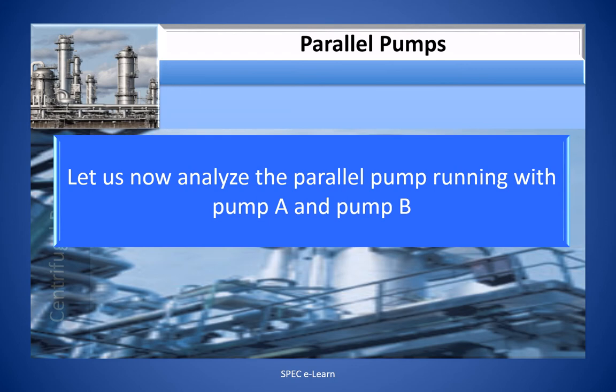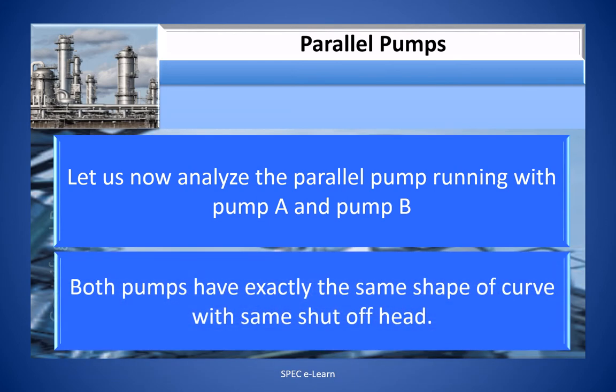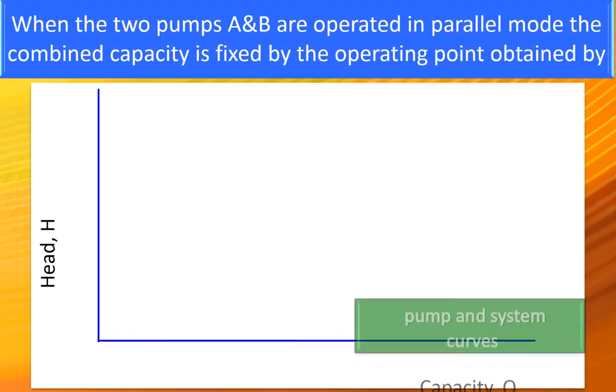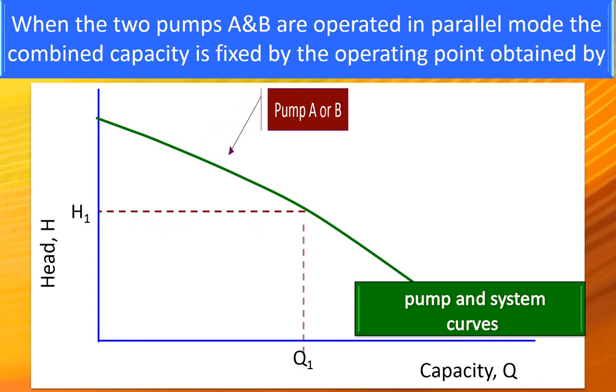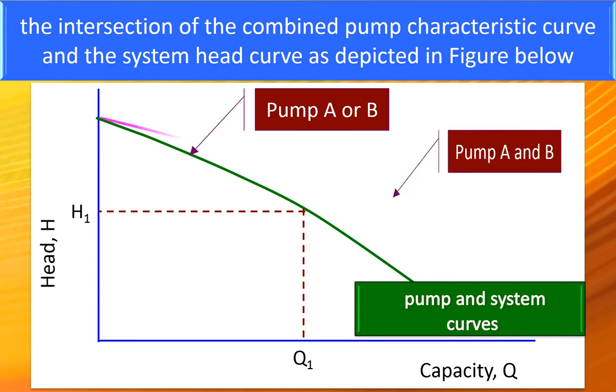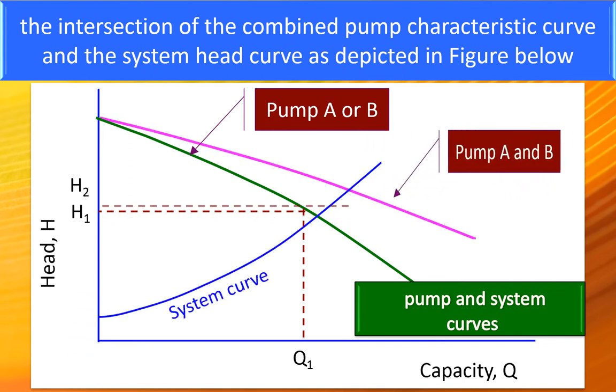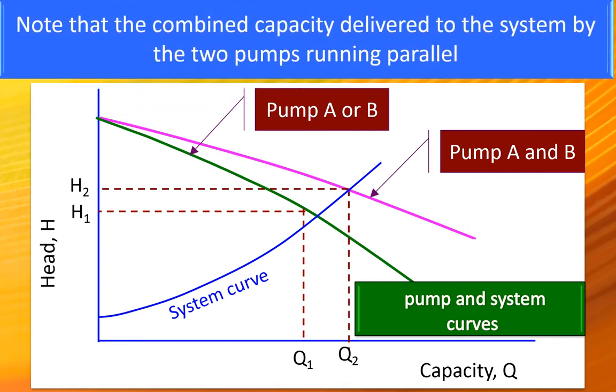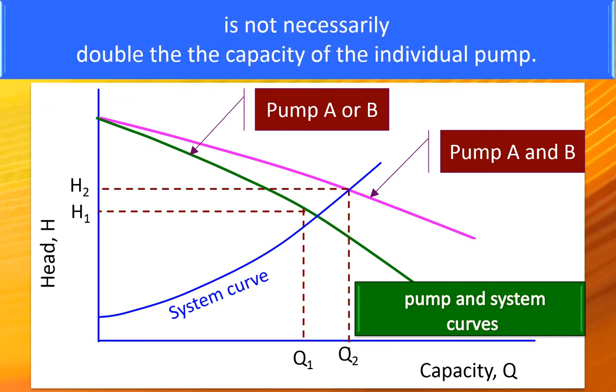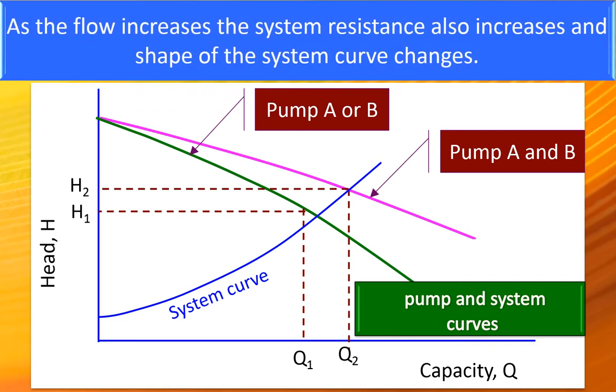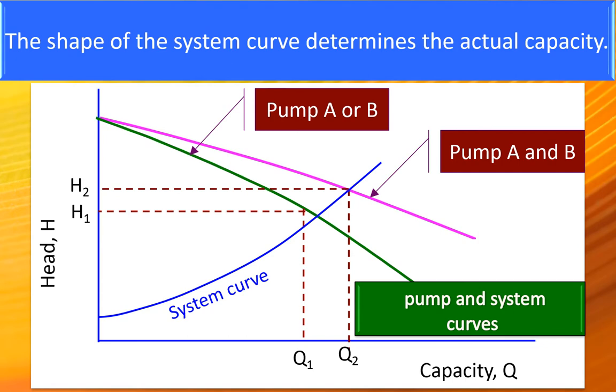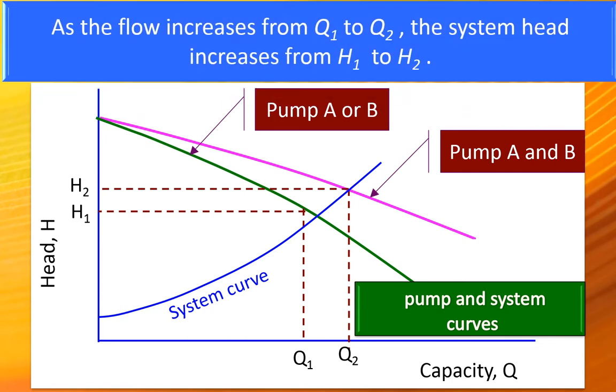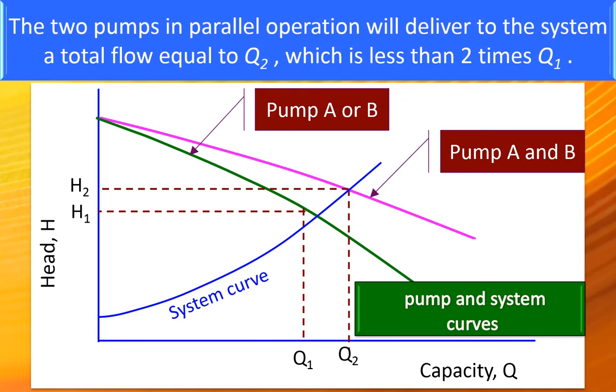Let us now analyze the parallel pump running with pump A and pump B. Both pumps have exactly the same shape of curve with same shutoff head. When the two pumps A and B are operated in parallel mode, the combined capacity Q2 is fixed by the operating point obtained by the intersection of the combined pump characteristic curve and the system head curve as depicted in the figure below. Note that the combined capacity delivered to the system by the two pumps running parallel is not necessarily double the capacity of the individual pump. As the flow increases, the system resistance also increases and the shape of the system curve changes. The shape of the system curve determines the actual capacity. As the flow increases from Q1 to Q2, the system head increases from H1 to H2. The two pumps in parallel operation will deliver to the system a total flow equal to Q2 which is less than 2 times Q1.